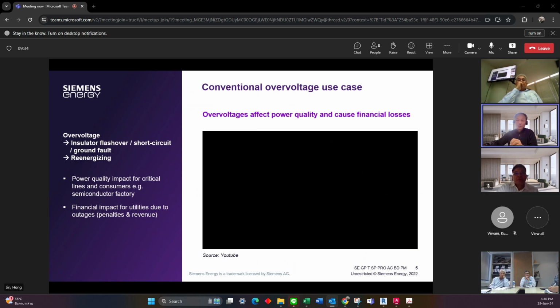And you can see that each flashover on the insulator will lead to a tripping failure on the overhead line. At least the circuit breaker on the power supply side must be opened to cut off the short circuit current on the insulator. And if the insulator has been damaged permanently, then this overhead line will not be able to be put into operation again. So this is the very high danger caused by the lightning overvoltage.